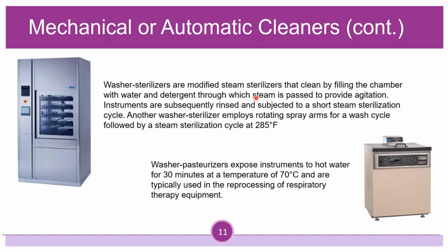Washer sterilizers are modified steam sterilizers that clean by filling the chamber with water and detergent through which steam is passed to provide agitation. Instruments are subsequently rinsed and subjected to a short steam sterilization cycle. Another washer sterilizer employs rotating spray arms for a wash cycle, followed by a steam sterilization cycle at 285 degrees Fahrenheit. And then washer pasteurizers expose instruments to hot water for 30 minutes at a temperature of 70 degrees Celsius and are typically used in the reprocessing of respiratory therapy equipment.